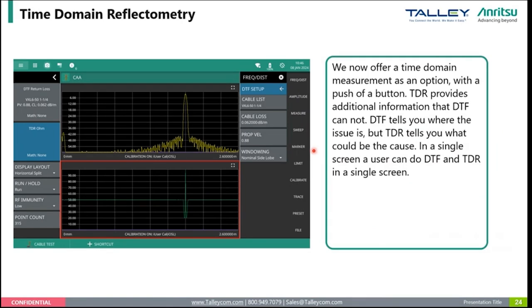We've added what's known as time domain reflectometry. This is really to replicate the impulse measurements from an actual TDR instrument. What we're doing is converting things into the time domain with a low pass step response to simulate the traditional TDR impulse measurements.